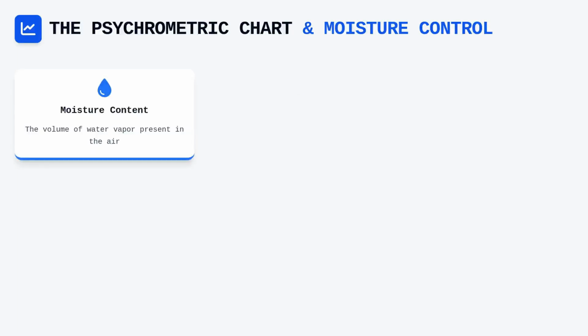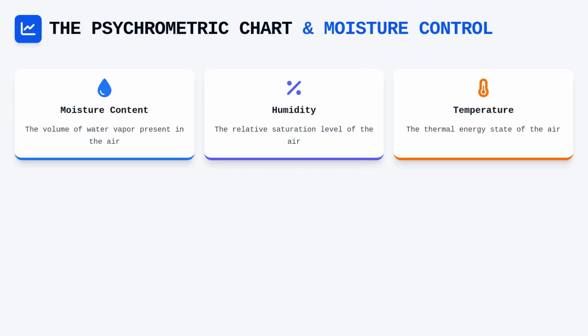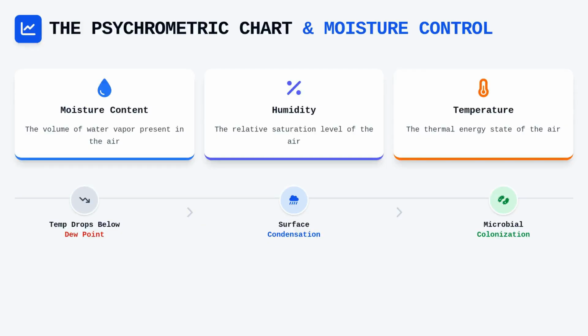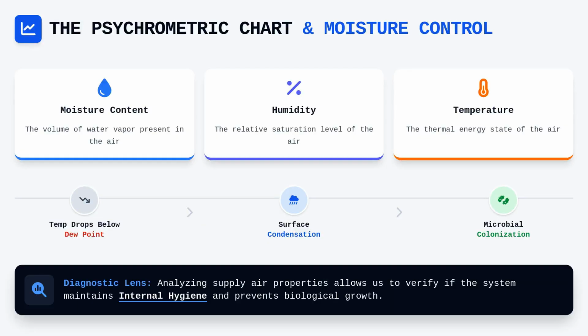The psychrometric chart is perhaps your most vital tool for understanding moisture control and preventing the conditions that lead to microbial growth. It maps the relationship between moisture content, humidity, and temperature, allowing us to predict when air will cross the dew point. When air temperature drops below this threshold, moisture condenses on surfaces, particularly on cooling coils or within cool duct interiors. This condensation provides the necessary liquid water for biological organisms to colonize, which is exactly what we aim to remediate. By analyzing the psychrometric properties of the supply air, we gain a diagnostic lens through which we can verify whether the system is operating within a range that maintains internal hygiene.